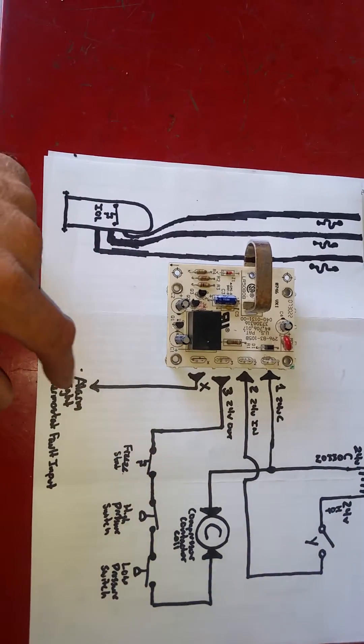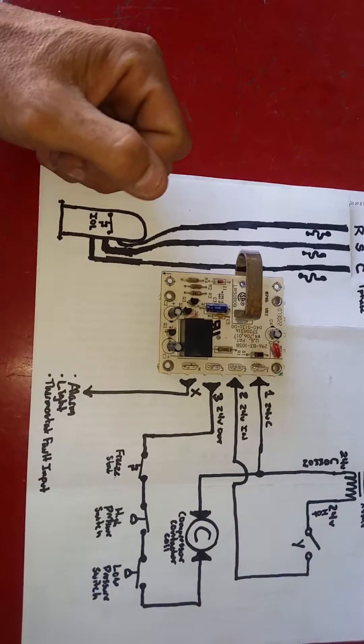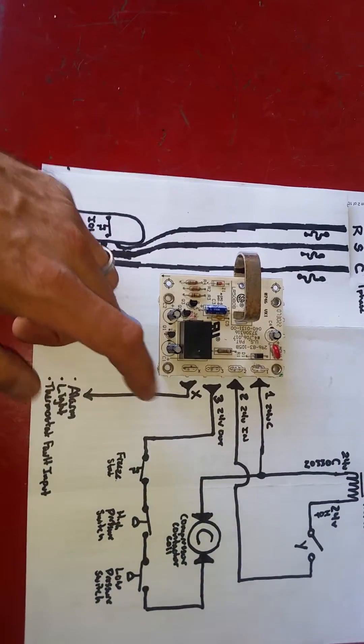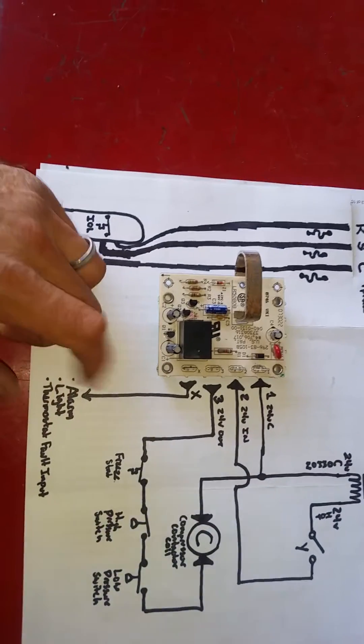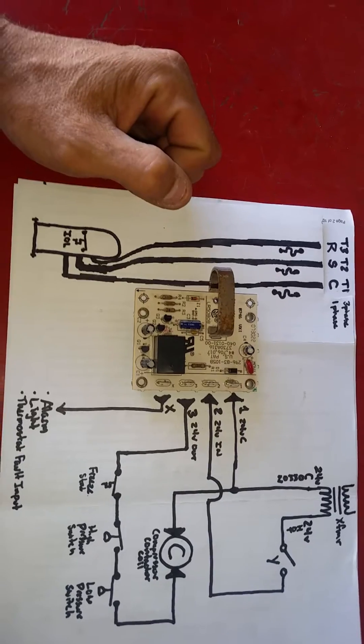We can send that 24 volts to that fault input to designate that there's an error or a fault with our system at the thermostat itself. Other times you can have this 24 volts go to an alarm, a light of some sort in order to signify that there's an issue with that rooftop unit.